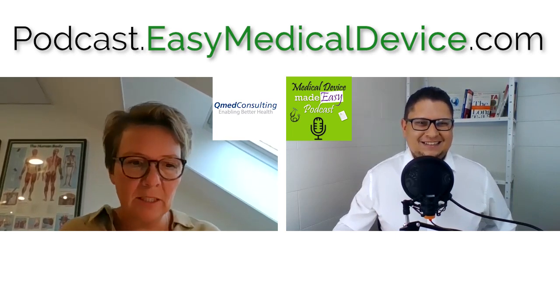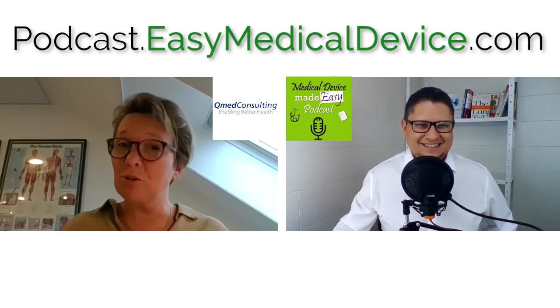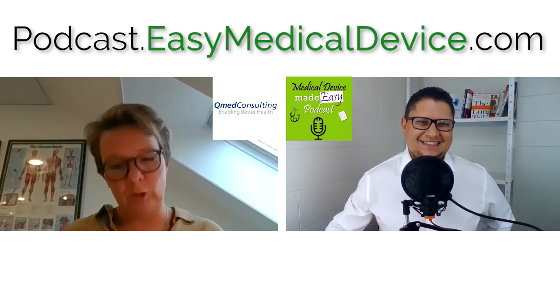Yeah, in one of the podcasts, I had Basil Akra from TÜV, and he actually stated that as a personal opinion, and where he's finding this in the MDR, he's a hotshot, so I listen carefully to what he's saying. It makes some sense, and I also looked into the wording. So for class 3 devices and implantable devices, no way, go and do a clinical study or investigation. For lower risk class products, if you can do that, you need to know the material, so biological, technical, and clinical. Clinical, you base that on publications, and you have the evidence from there that is used on the same population and age and all these things. And the technical you get from reverse engineering. Yes, you buy it, you split it, you measure it, and you test it, then you can do it. That's how he interpreted the text, and I can also read it from the text.